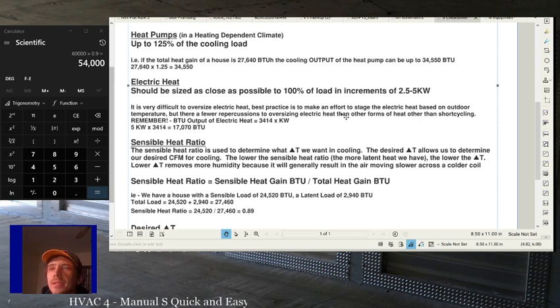The best practice with it is to make an effort to stage the electric heat based on outdoor temperature. So, for instance, if a house has a heating load of 60,000 BTUs and the heat pump can put out 37,000 BTUs at 47 degrees outside, then you might only want to let the first stage run until it gets colder outside. So once it gets below 47 degrees, then you allow the second stage to come on. Now that requires you to have outdoor thermostats that are wired to the electric heat to lock out stages based on outdoor temperature. But if you do that, your equipment will run longer. It'll be a more even heat in the house. It'll be more comfortable, and you'll get better performance and more energy savings, right?